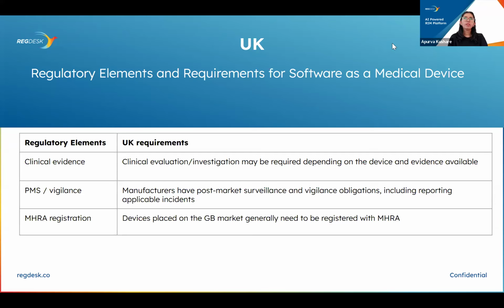And also, one important thing to note, before registering a device with the MHRA, you should consider if your device is placed on the market, put into service, or both. If a medical device is put into service or placed on the market, then you must register the device with the MHRA.